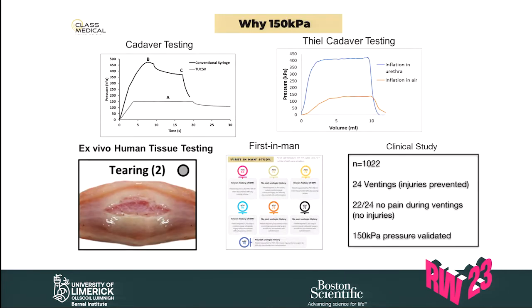And then finally, because we had 24 ventings and in 22 of the 24 there was no pain, we argue that this validates that the threshold is a good threshold because there was no damage to patients. The reason I'm labouring this point is the FDA is arguing with us at the moment. So it doesn't have FDA approval, but it has been CE marked nearly 2 years ago now.